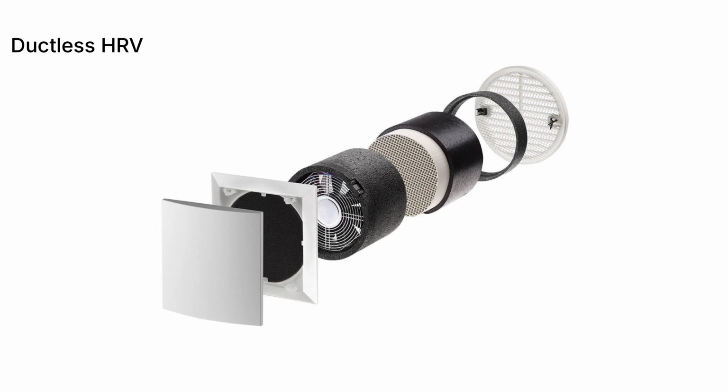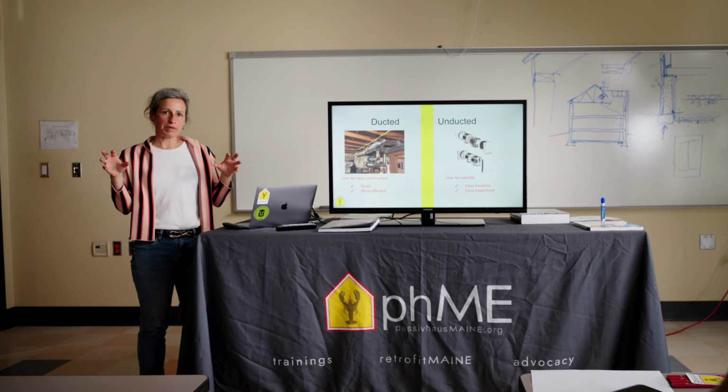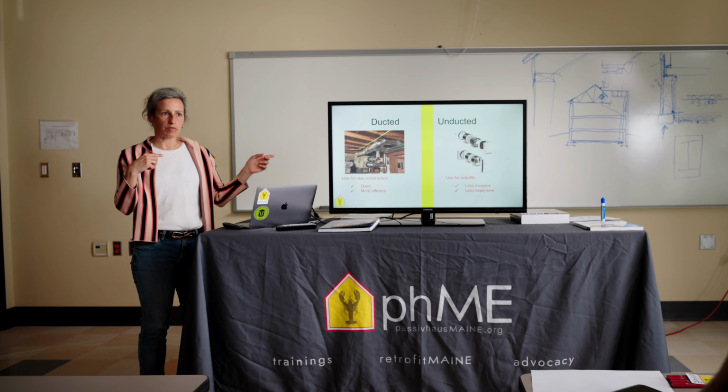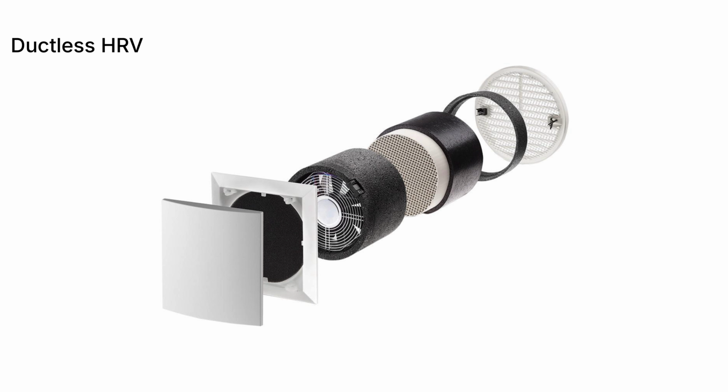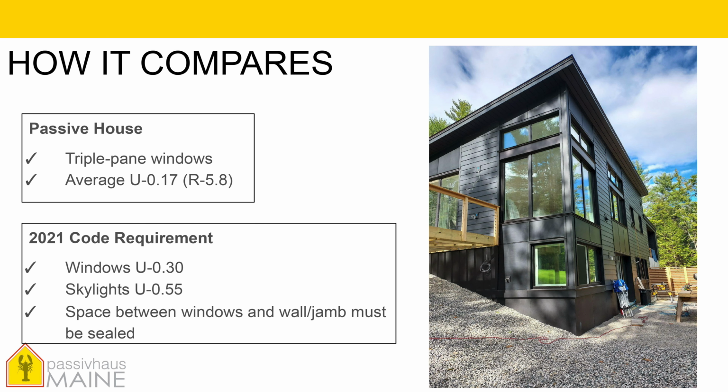It has a core that you can kind of see there. Set them up in pairs. It spends 90 seconds with one sucking air in, the other one blowing air out. As it's blowing the air out, it heats up the core, and then 90 seconds later or something, they in sync switch directions, and so the air coming in is now passing over the core that just spent 90 seconds getting heated up, and the other one's blowing out. So they can actually get super efficient.